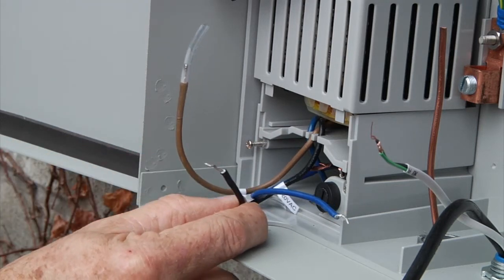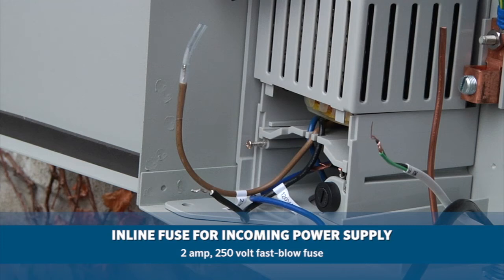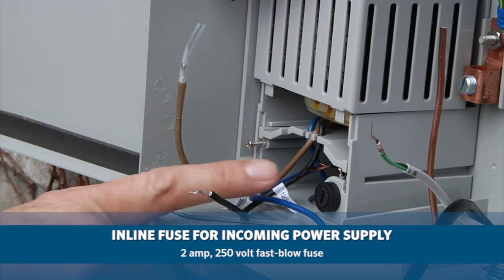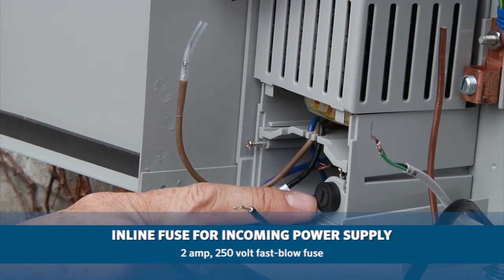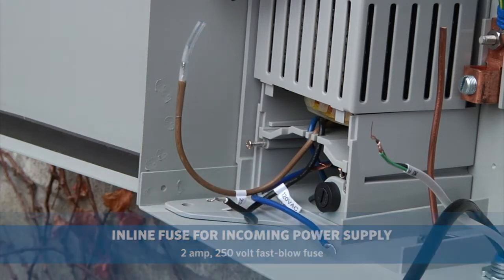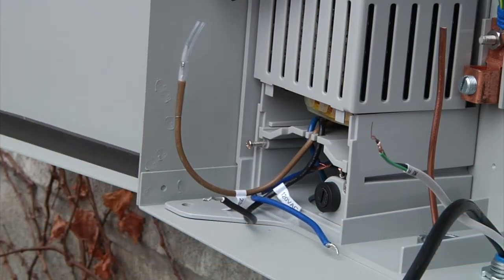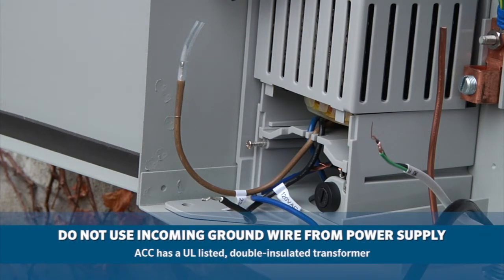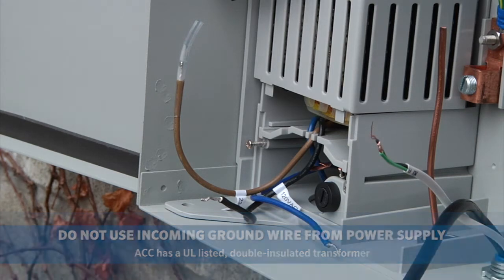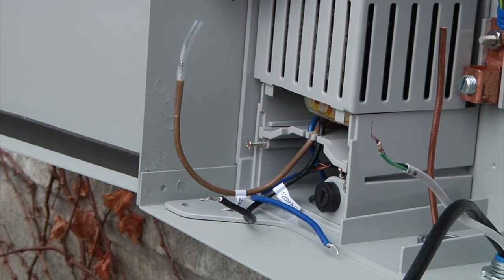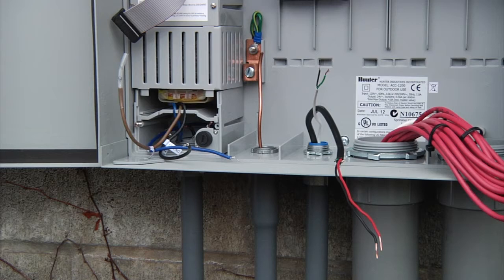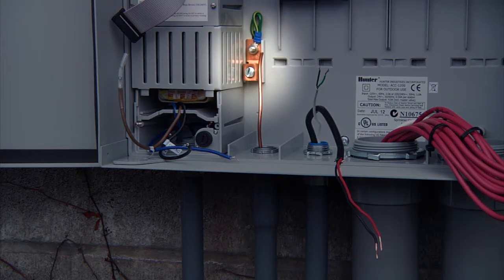Now to the right, there's also an inline fuse for the incoming power supply, and that is a 2 amp 250 volt fast blow fuse, and by popping that fuse out, it will kill the power for the entire controller. Now don't forget, on the incoming power supply, you will not use the incoming ground wire from your supply. The ACC has a UL listed double insulated transformer and does not need the use of that green ground wire coming in. There's an earth ground lug to the immediate right of the transformer assembly.